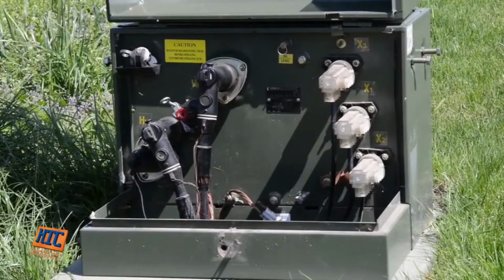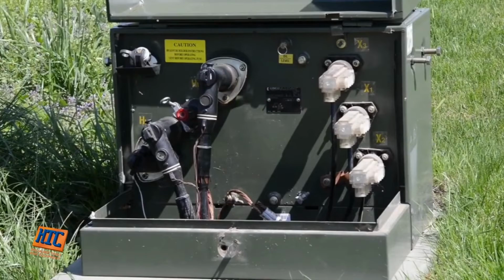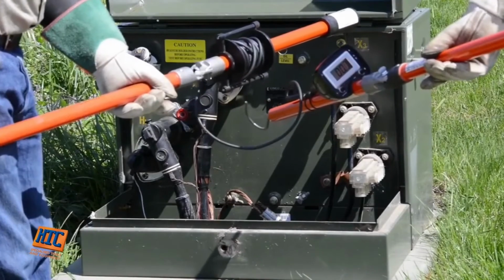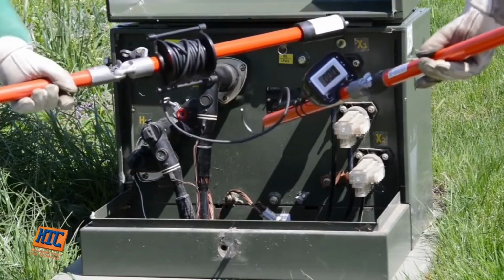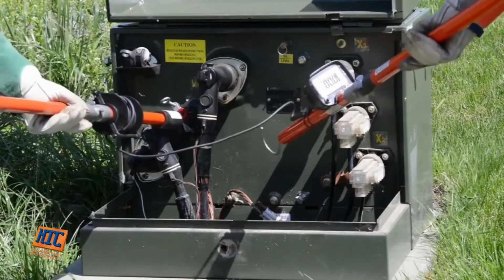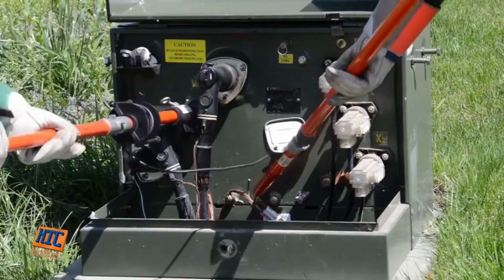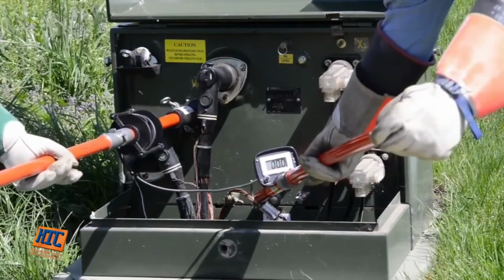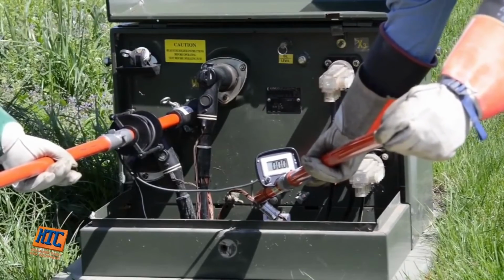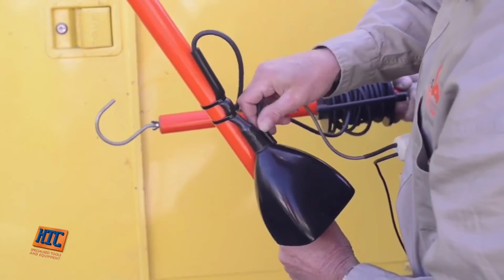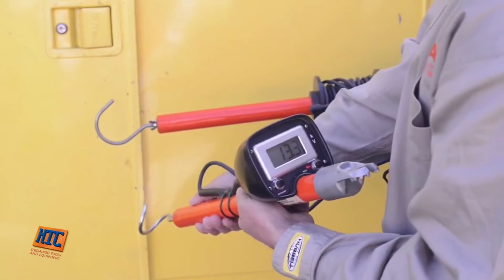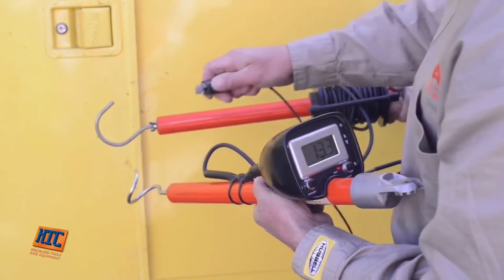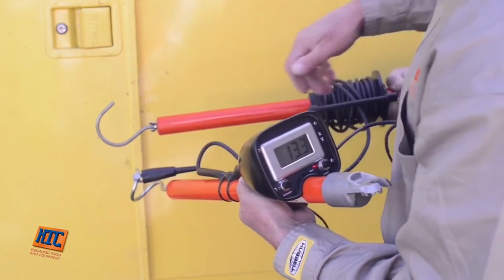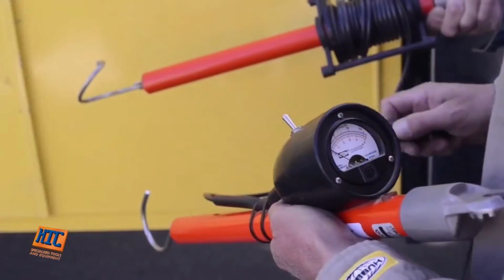Now, here's the same procedure using the digital phasing tester. Again with the bushing adapter fitted on the reel stick, the probe is inserted into the feed-through bushing and the meter probe is contacted with the system ground. Again, the 0 reading indicates there is no voltage present on the cable. After each use, verify the phasing tester is fully functional, again with the voltmeter tester for phasing testers, as listed in the instruction manual provided with each, whether the analog or digital type.